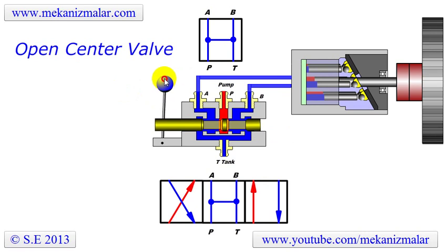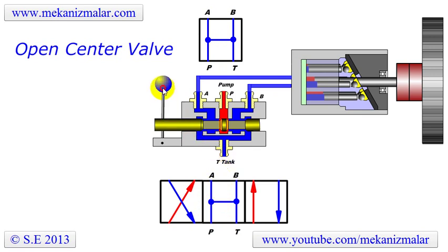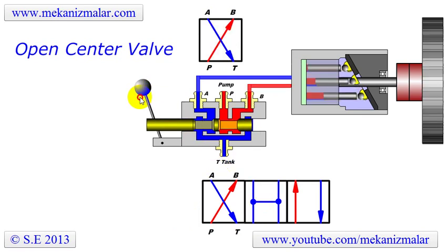On occasion it is called the H-valve, in reference to the four-port connection form in the valve center position. It is seldom used to control hydraulic cylinders, because of the piston drift when the valve is in the center position.